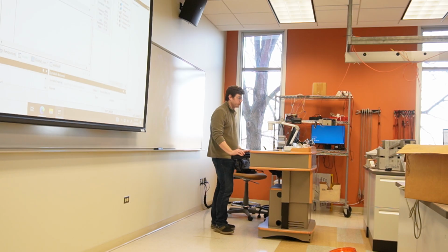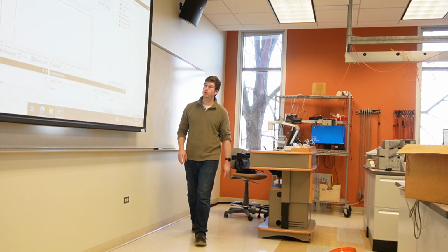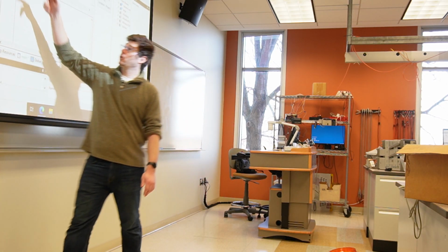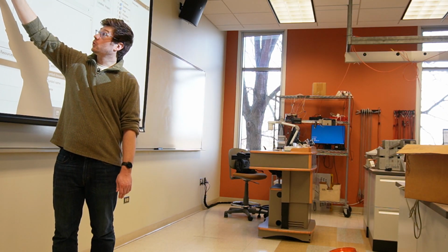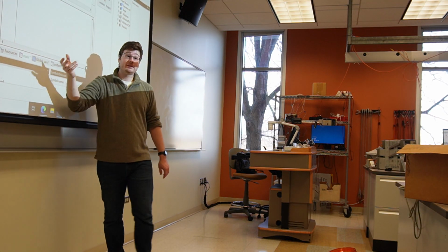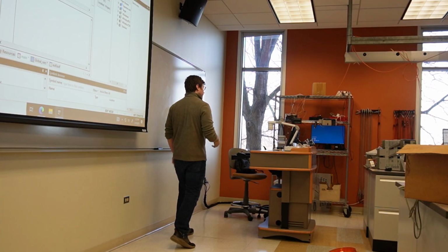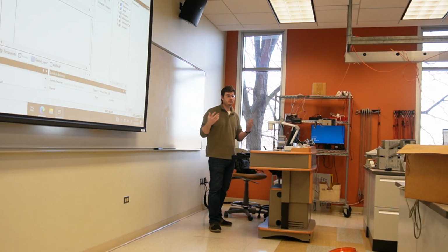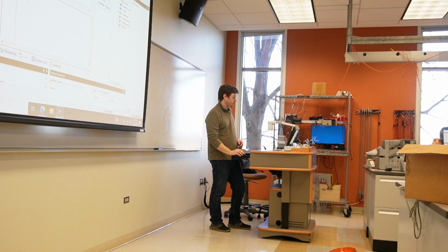By dragging it into the group just like that. Okay, I'm gonna do that one more time. So main, I'll also drag in that group. Now my program asfast is in there, and so is main. Both of these programs, this program will be run first, then this program will be run, and that takes as long as it takes. Ideally less than 10 milliseconds, so at the next trigger, it'll start again, right?